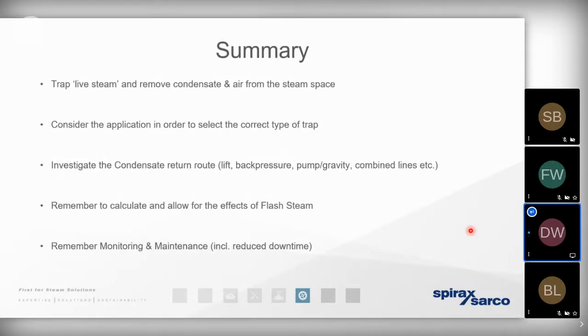Hopefully it's given you a better insight with regards to what's important with regards to sizing, selecting and installing steam traps. I'd just like to remind us that the main purpose of a steam trap is to remove condensate, but also to help with the passage of air from a steam distribution network. Some steam trap types are very, very good at venting air. Other steam trap types are not. So it's for that reason that we always encourage you to consider air venting as an entirely separate issue. We're aware of the value of removing the condensate, so we want to ensure that we get the condensate back to the boiler house as quickly as possible.